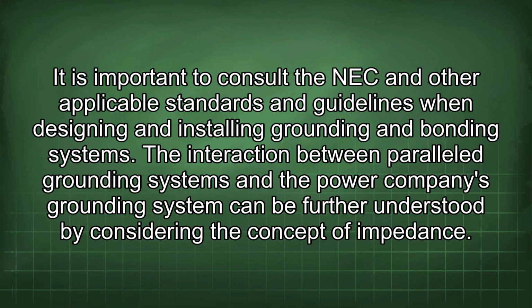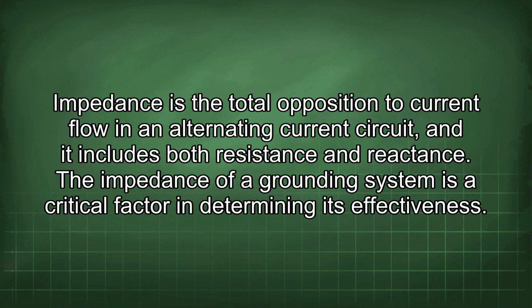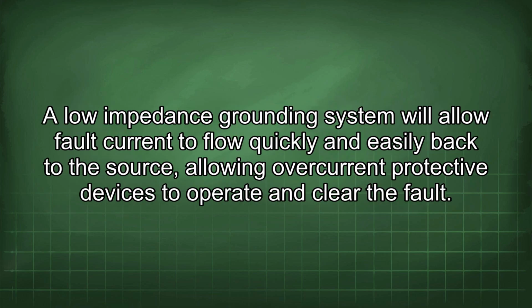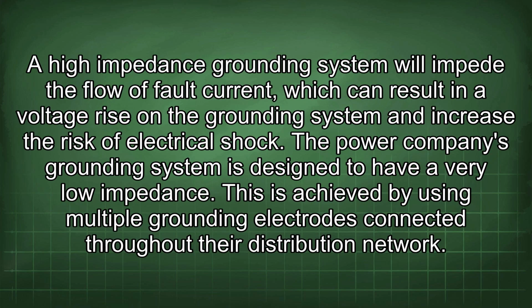The interaction between parallel grounding systems and the power company's grounding system can be further understood by considering the concept of impedance. Impedance is the total opposition to current flow in an alternating current circuit, and it includes both resistance and reactance. The impedance of a grounding system is a critical factor in determining its effectiveness. A low impedance grounding system will allow fault current to flow quickly and easily back to the source, allowing overcurrent protective devices to operate and clear the fault. A high impedance grounding system will impede the flow of fault current, which can result in a voltage rise in the grounding system and increase the risk of electrical shock.